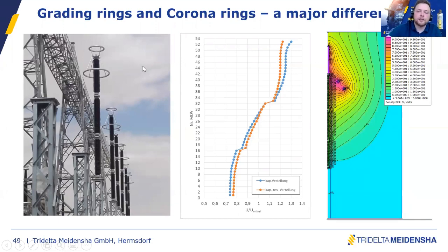And through those capacities, a current is flowing because we are living in the AC world. Current can flow through the air, through the capacity of the air, and also through the surge arrestor itself. So we have a resistive, capacitive voltage distribution along the surge arrestor. And the highest capacities occur on top, so the highest currents do flow on the top of the surge arrestor. All the capacitive current and resistive current that flows through the lowermost zinc oxide block has also to flow through this. On this diagram, we have 54 MOV blocks. All those 54 MOV blocks have a capacitive current and a resistive current, and the top MOV block has to take all the current of those.